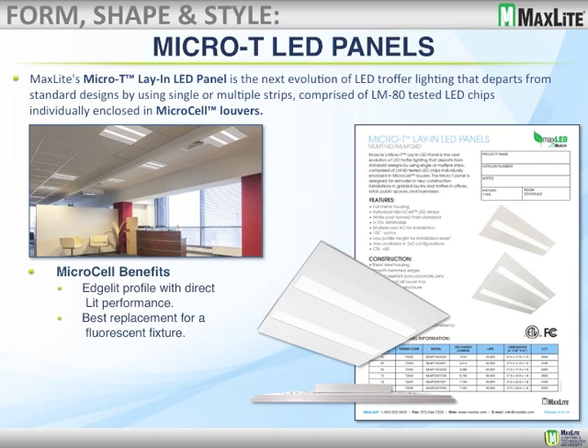The Micro-T features a really unique optic called the Microcell. In each white strip of a 2x2 fixture, there are about 70-plus LEDs that are about an inch away from the diffuser surface. Normally that would cause a lot of glare and focus light in a tight 120-degree beam angle. But the Microcell optic diffuses the light evenly — even though it's only an inch from the surface, you can look directly at the LEDs with no real visible glare. It has a very warm and inviting appearance, and efficiently distributes the light for a good fluorescent replacement.